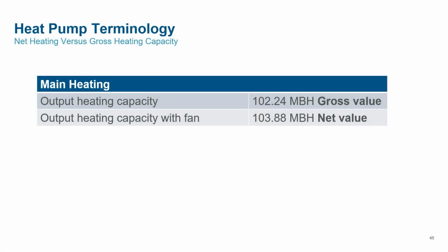Next, we'll take a look at net heating versus gross heating capacity. When considering heat pump applications, it may be common to see a higher net heating capacity than a gross heating capacity. The inverted capacities may seem counterintuitive, but not with a heat pump. In the cooling mode, the indoor motor heat impacts the cooling capacity. The additional heat is captured in the equipment's net total capacity output.